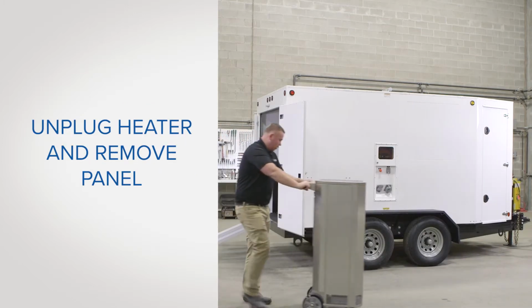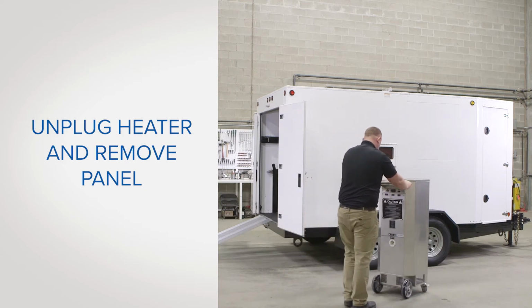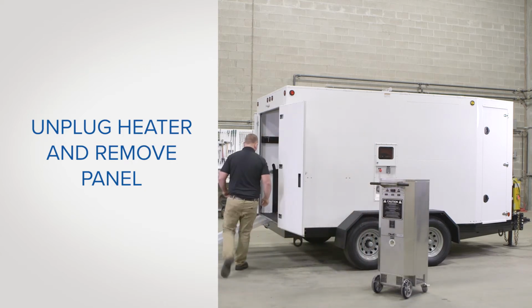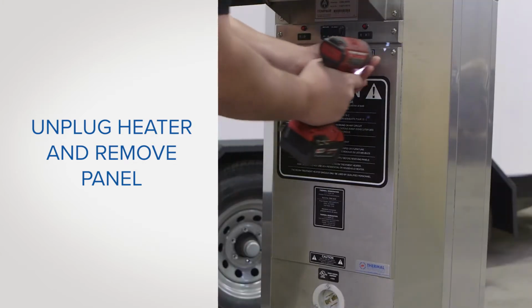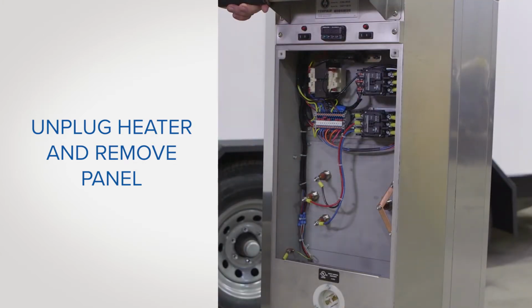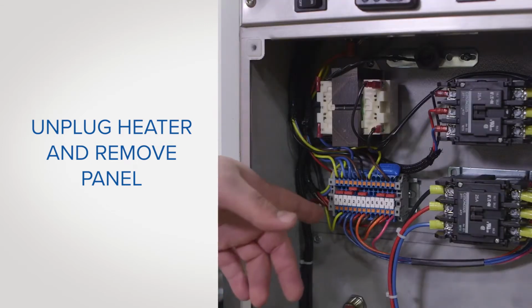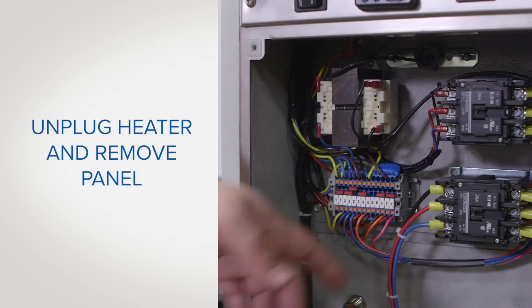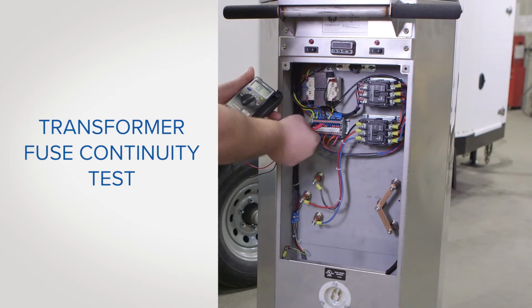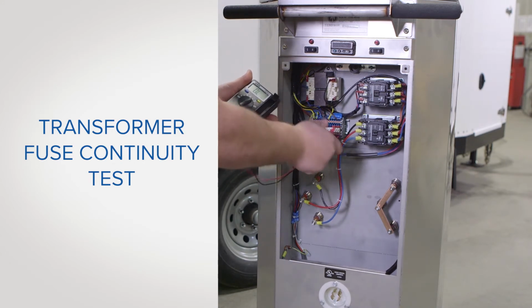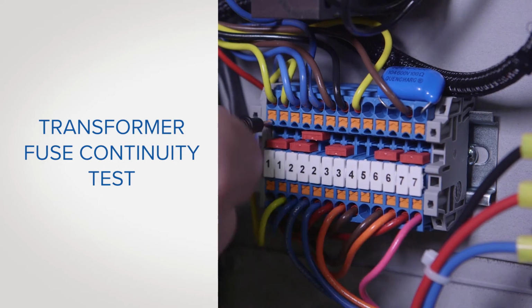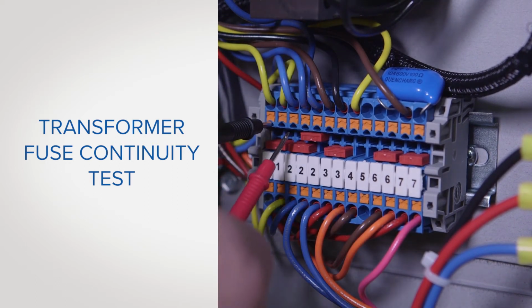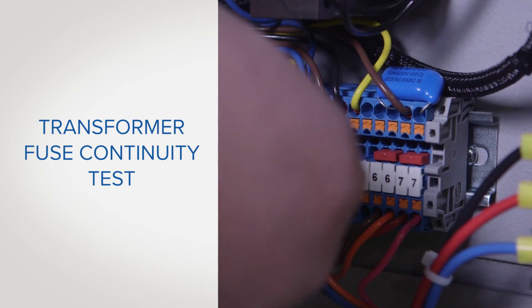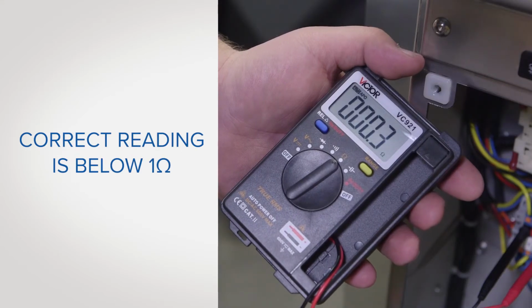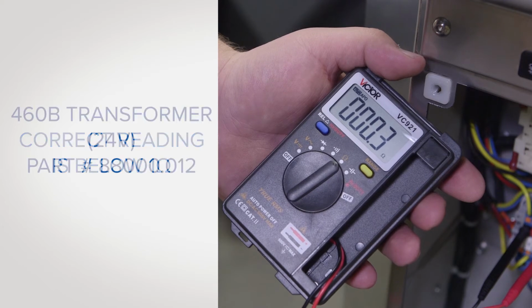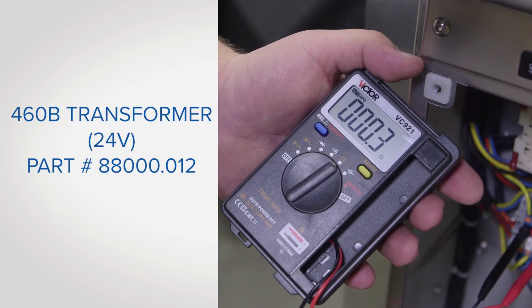If your heater is not operating properly, there are several tests you can perform. The following tests should be performed with a digital multimeter with the heater unplugged. The first 3 tests are to be performed on the terminal test strip. To perform the transformer fuse continuity test, place an ohm meter on the lowest scale and measure between terminal 1 and the first terminal 2. The reading should be below 1 ohm of resistance. If the meter reads open, the fuse is blown inside the transformer and you will need to replace the transformer.